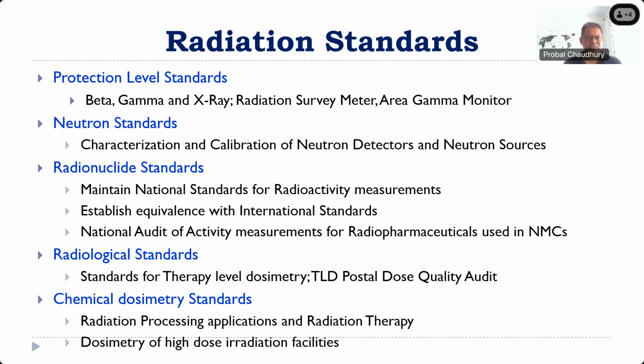All this is protection level equipment. They are mainly for beta, gamma, and X-rays, and include radiation survey meters and area gamma monitors. In any radiation facility where you are working, you have to have area gamma monitors installed so that the radiation level is monitored all the time, and if there is any increase in the radiation level, we get an alarm so that corrective action can be taken immediately. This is a mandatory requirement for all radiation facilities, to be fitted with area gamma monitors, and of course personal dosimetry. Then coming to neutron applications, we have the neutron standards group, which mainly deals with the characterization and calibration of neutron detectors and neutron sources.